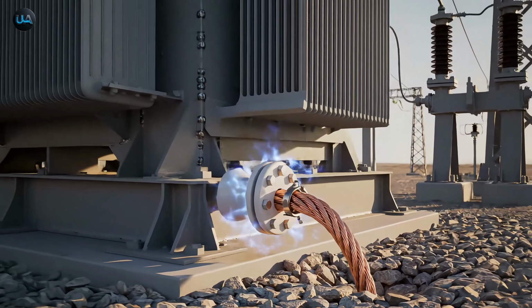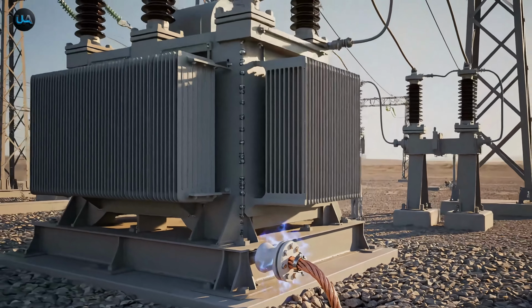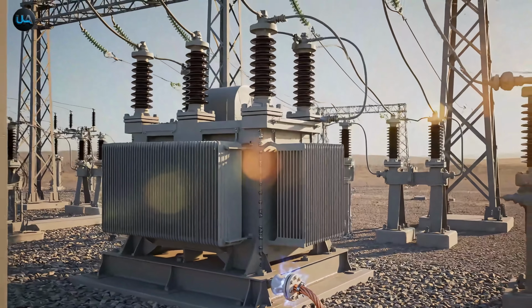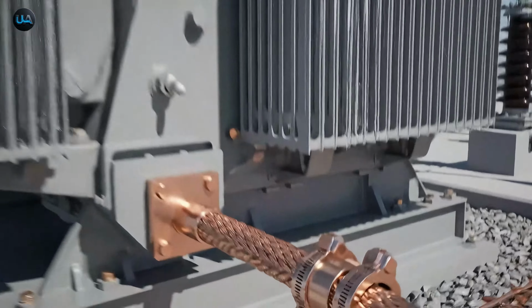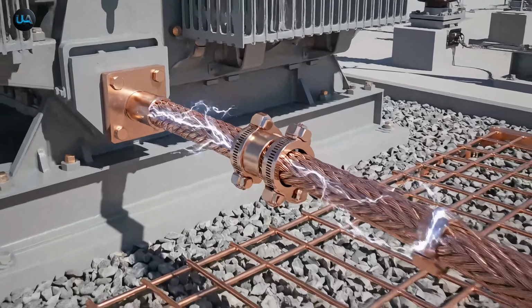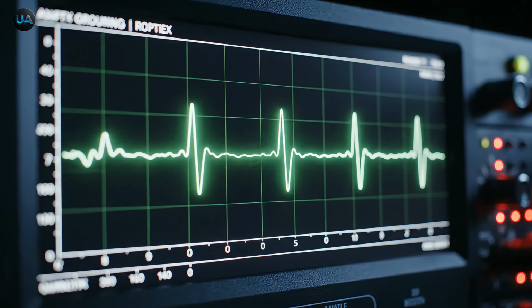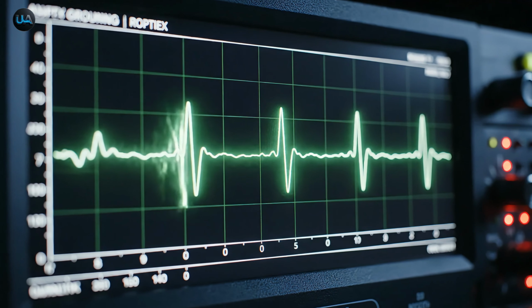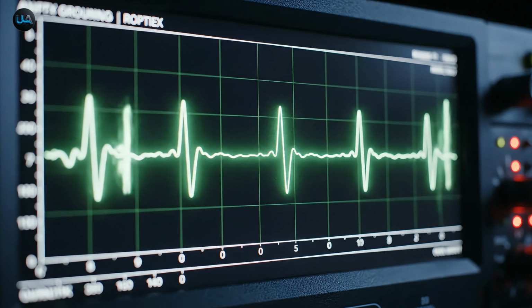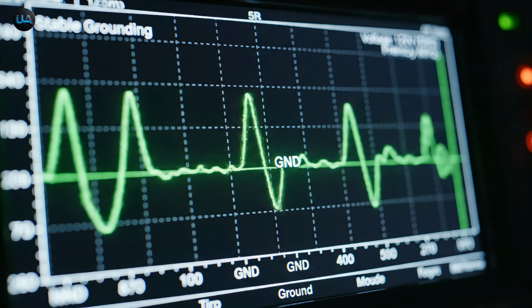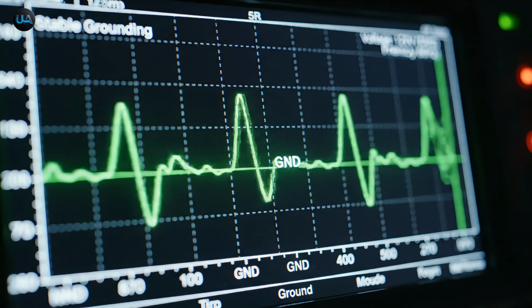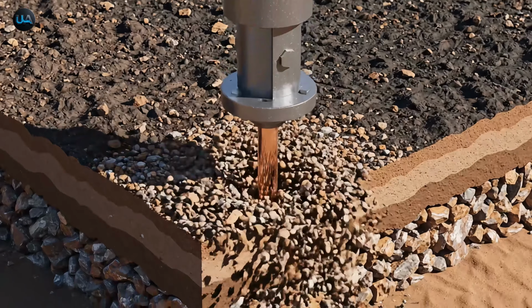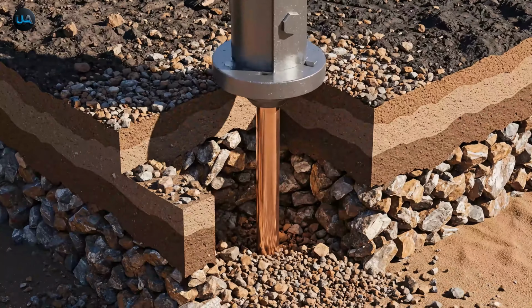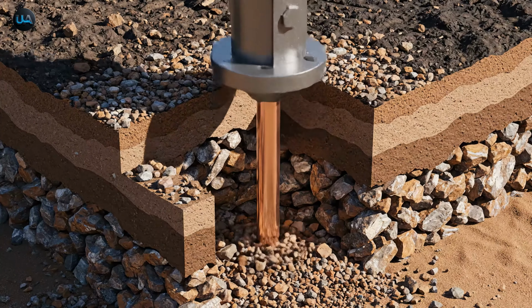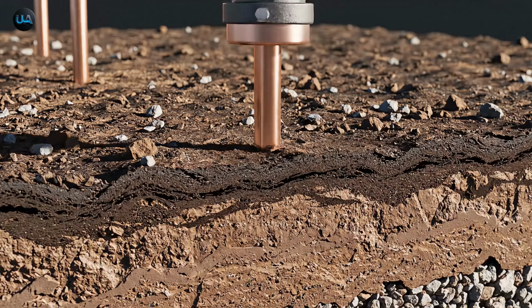System grounding is about stability. It involves grounding one of the current-carrying conductors, typically the neutral wire, at the source transformer. This stabilizes the system voltage. It prevents dangerous voltage swings on the live conductors, reducing stress on the insulation of the entire electrical network. The primary component is the ground electrode, a copper rod or plate driven deep into the earth to ensure a reliable electrical connection.